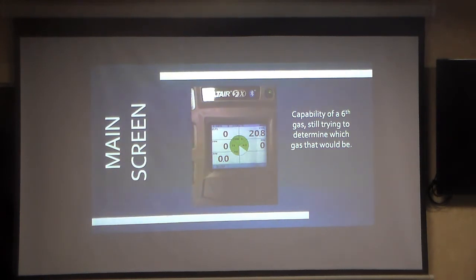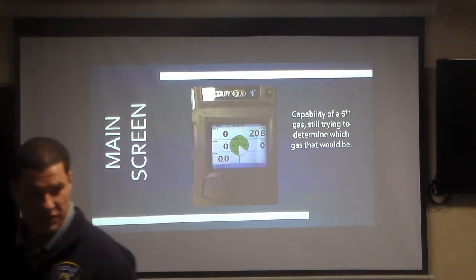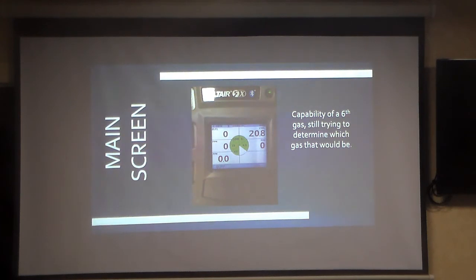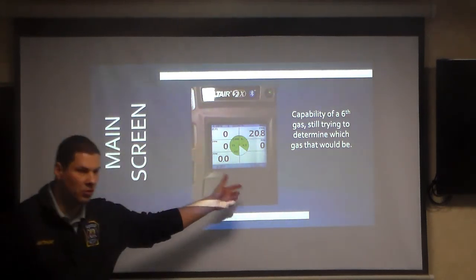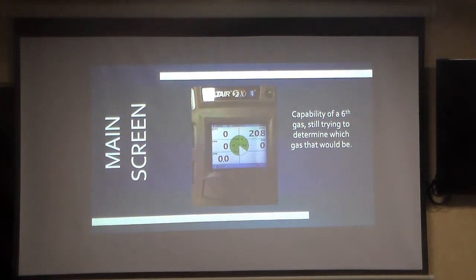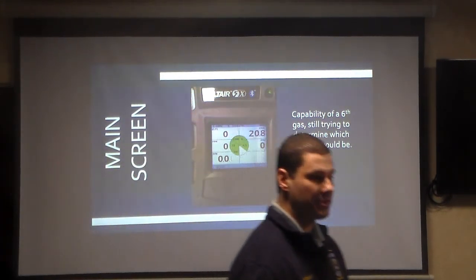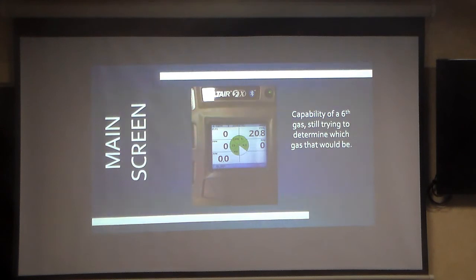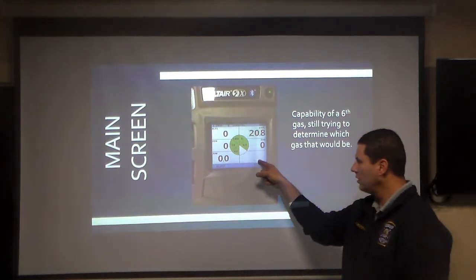So you saw the fresh air setup, and there's a yes or no option. You just click the power button below the appropriate one, and now you're in metering mode. If you don't hit anything, it'll default to the previous fresh air setup. I would not trust that, because you have no idea who turned it on last, or where they were at. As you see up here, there's capability for a 6th gas, which would be right here.